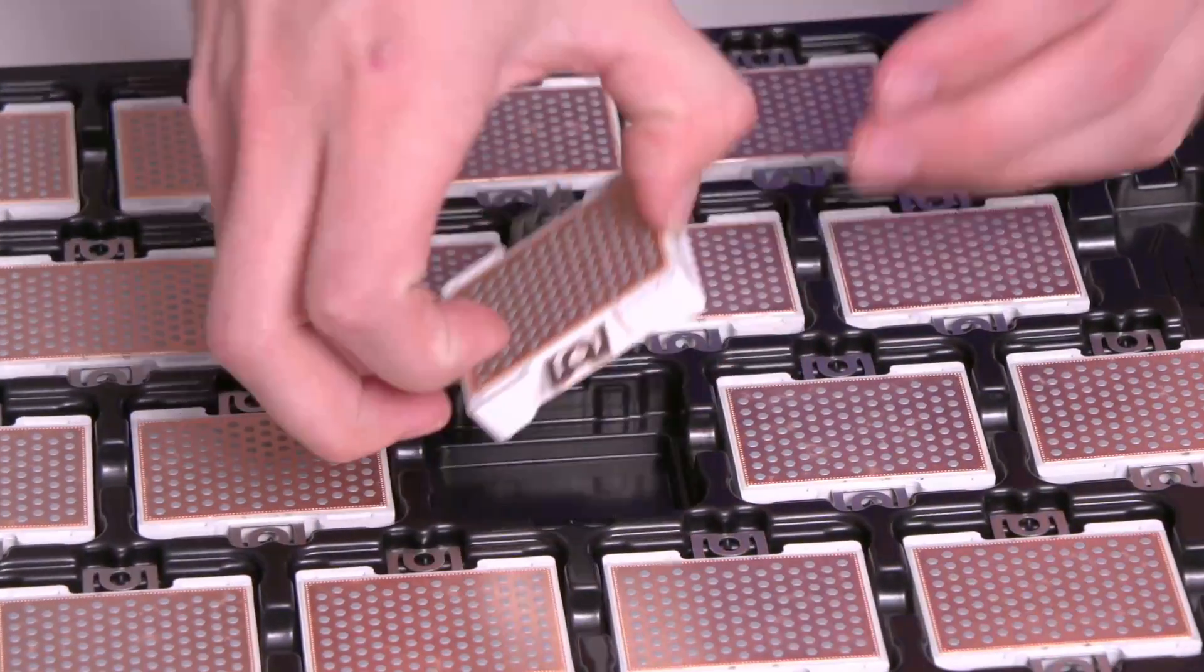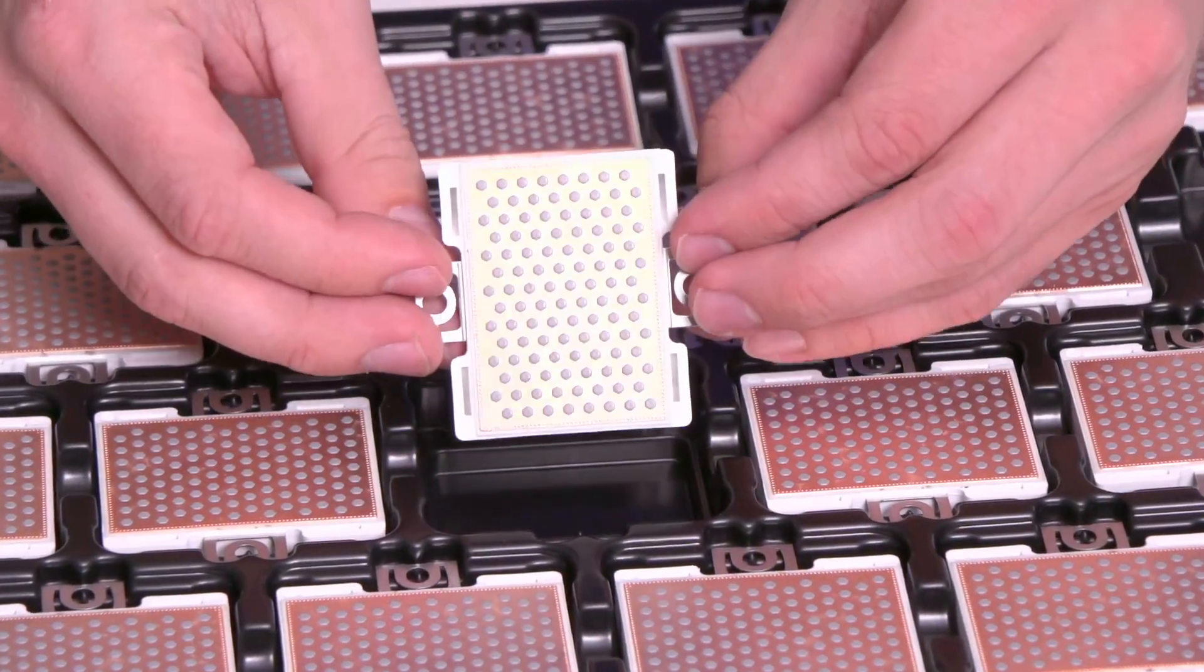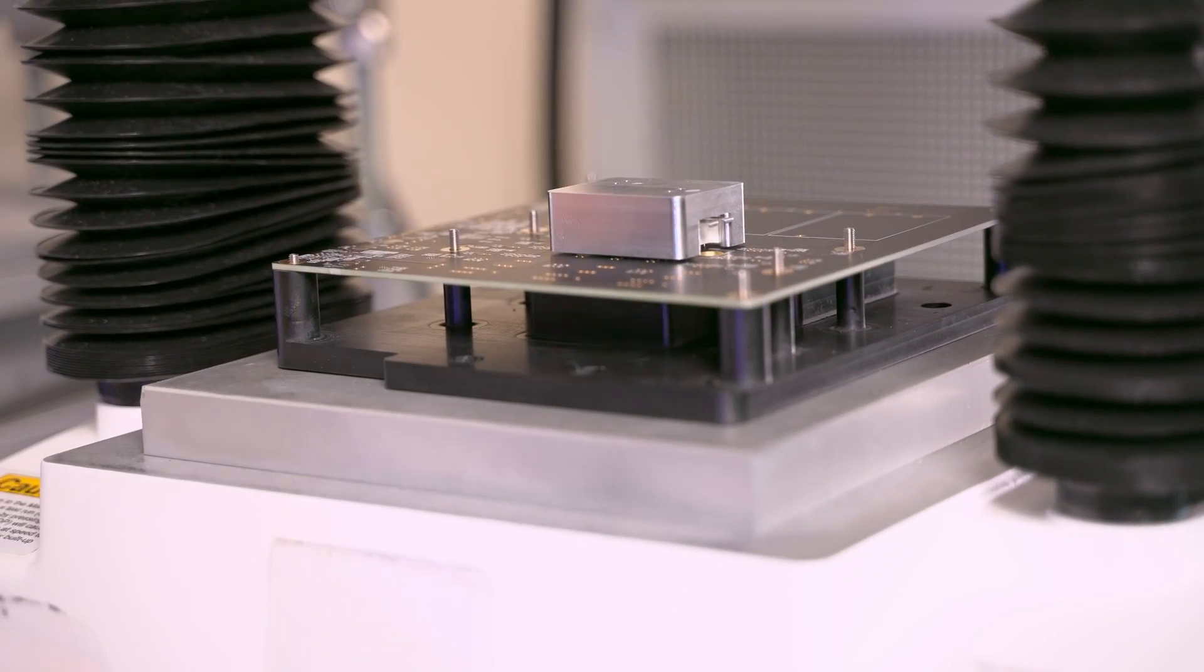If the modules feature pre-applied thermal interface material or TIM, you will need to develop press-in tooling with proper locating and tolerancing of the internal cavities to provide a sufficient press area. This will avoid interference with the TIM pattern.